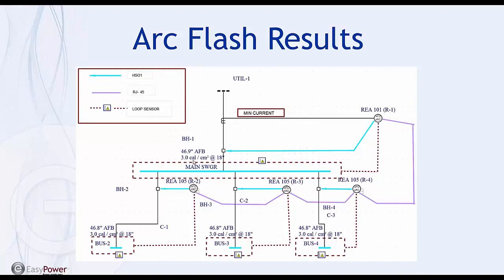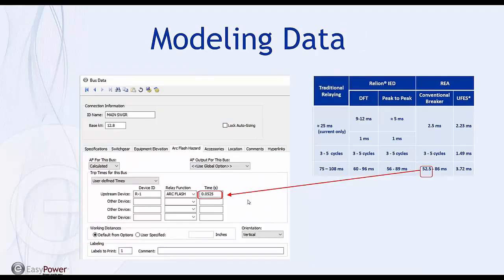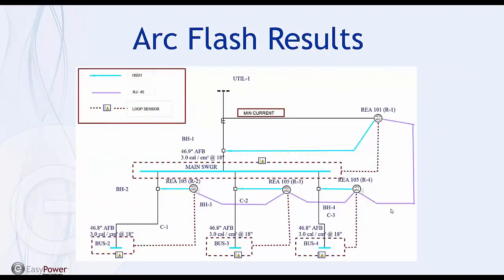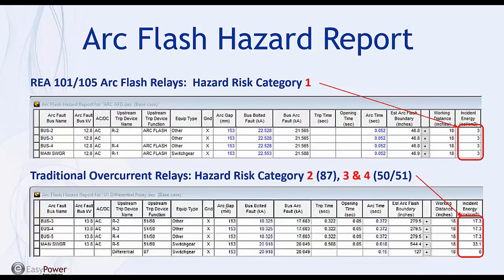The incident energy here is 3 calories per centimeter squared for both the main switchgear and all the buses. And that's for the operate time that you saw on the previous slide of 0.0525 seconds, or 52.5 milliseconds. So once we run the arc flash study, then you can see the arc flash report. We ran the arc flash study and looked at all the devices. Here's the incident energy for the REA devices, the main and switchgear and the 3 buses. And here's the arcing time, which consists of how long it takes the REA to operate and the breaker time collectively. That information is provided here, and you can see the resultant incident energy.